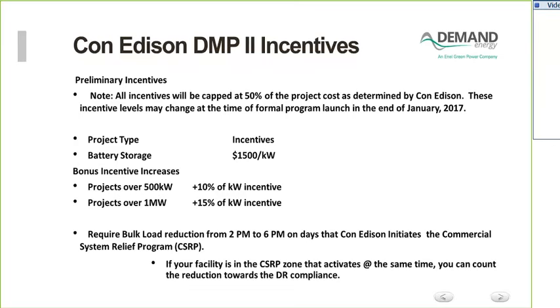For us, as we operate under standby, every day we're driving demand charge savings, and they'll give us notification 21 hours ahead of time. We'll know tomorrow's going to be an event, so we'll forego the demand savings for that day and operate under the bulk dispatch they've asked for from 2pm to 6pm. We'll only lose one day of demand savings instead of losing the demand charge for the entire month, because if we weren't on standby, the likelihood we'd hit a peak on a CSRP day is really high. So we lose savings for that one day we don't participate, but the next day, if they don't call an event, we go right back into demand charge savings. That's what we like about standby: the operational flexibility it gives us in how we approach the market.